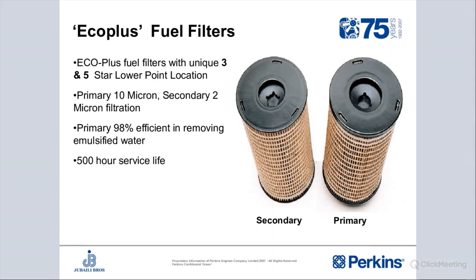The fuel filters, the primary and secondary: this one is a 2 micron filter, this one is a 10 micron filter. Here we have 3 notches, and here we have 5. Inside their canisters we have probes at the bottom. This filter would not fit on the primary canister instead of the other one, because the number of notches on the probe must match the number of notches on the filter.